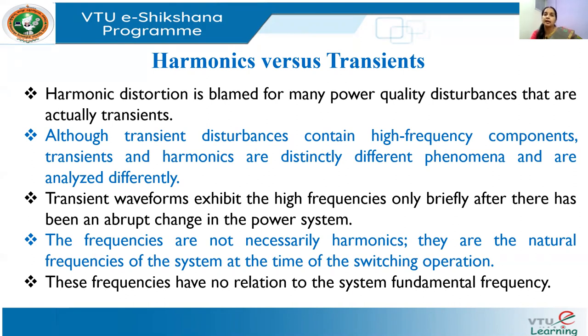Transients are caused by sudden or abrupt changes in the system. Even though transient waveforms exhibit high-frequency components, these frequencies are not necessarily harmonics — they are not generally integer multiples of the fundamental frequency. They may be very random in nature and have no relationship to the system fundamental frequency. Harmonics, by definition, must be integer multiples of the fundamental frequency.